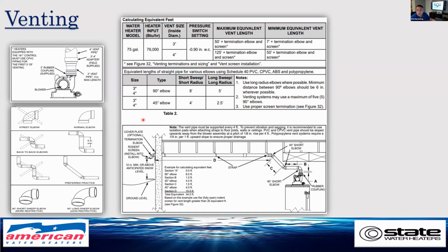In this chart, I'd like you all to take notice that your fittings and elbows do account for equivalent feet inside of the venting run. So a short pattern 90 would be equivalent to 8 feet. A long radius one would be 5 feet, and your 45 would be 4. I also want you to look at section A right here. 6 inches minimum.